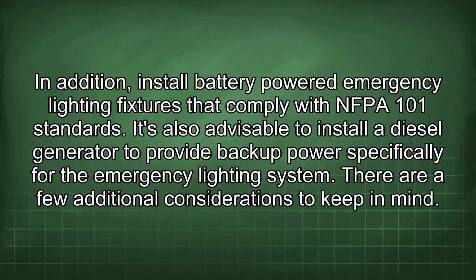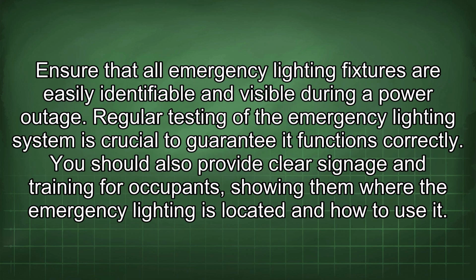There are a few additional considerations to keep in mind. Ensure that all emergency lighting fixtures are easily identifiable and visible during a power outage. Regular testing of the emergency lighting system is crucial to guarantee it functions correctly. You should also provide clear signage and training for occupants, showing them where the emergency lighting is located and how to use it.